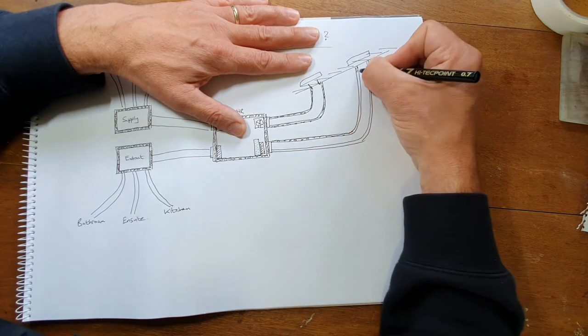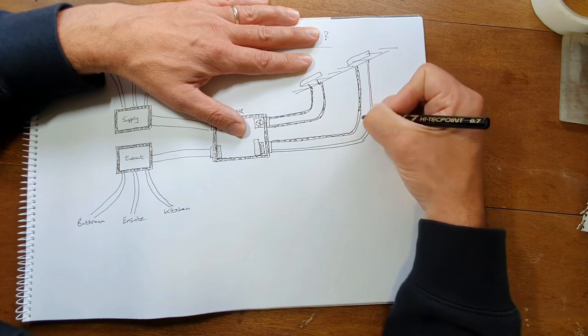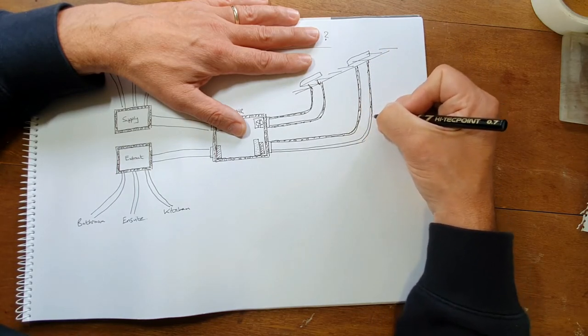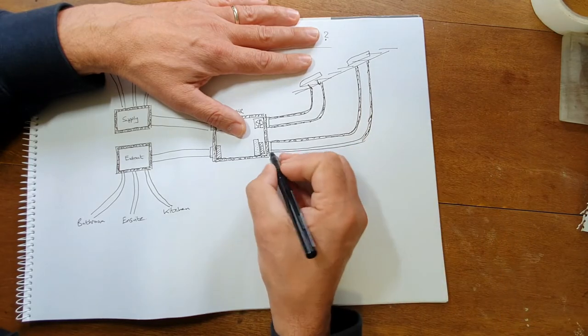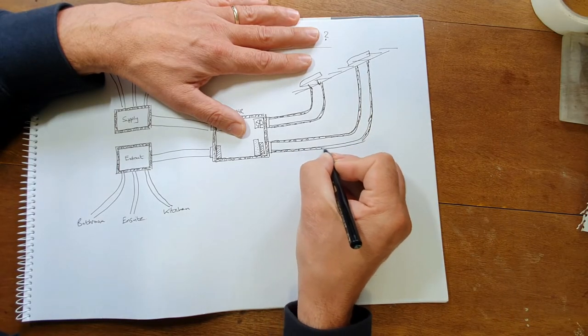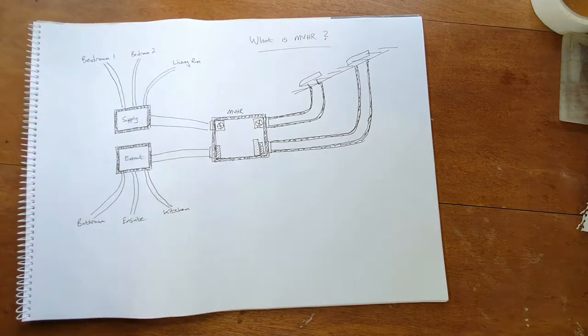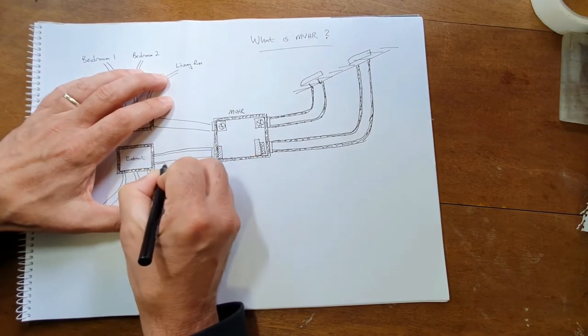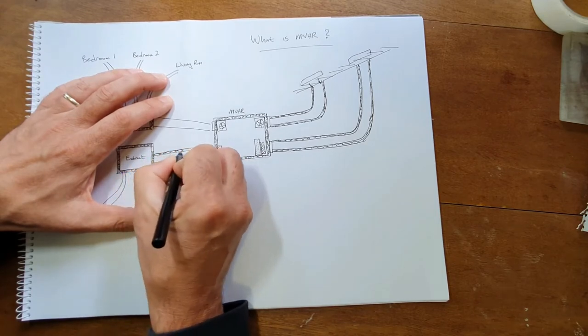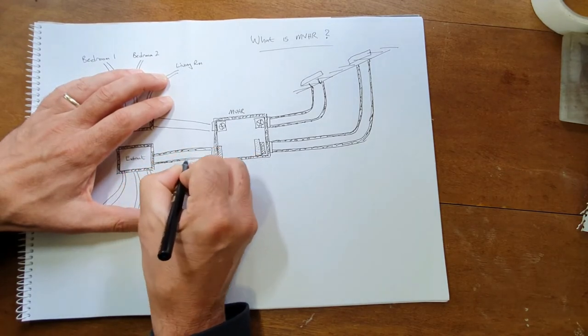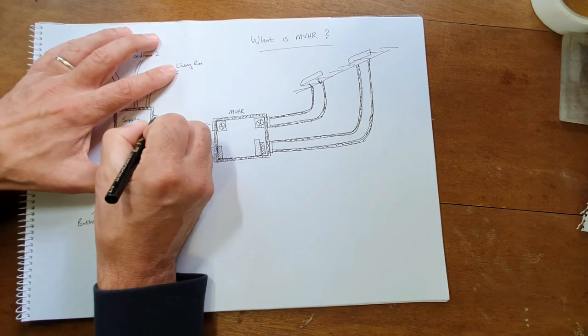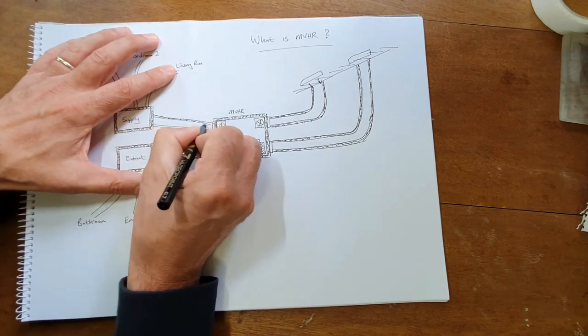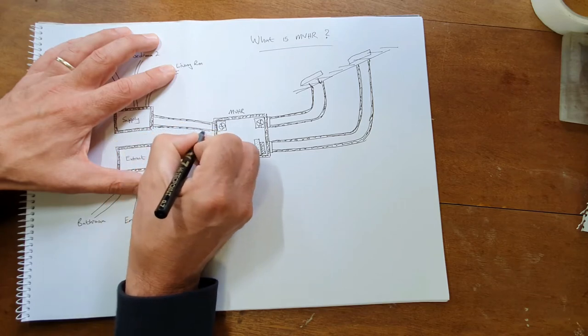Typical duct insulation there is either expanded polyethylene, expanded polypropylene or it's a steel duct if it needs to be more durable. It's going to be boxed in for example and that would have a jacket around it to keep it warm. We also put duct insulation on the pipes that go to the manifolds normally. That's to help reduce the motor noise, breakout noise it's called, from the MVHR fans. Never have too much soundproofing on an MVHR.